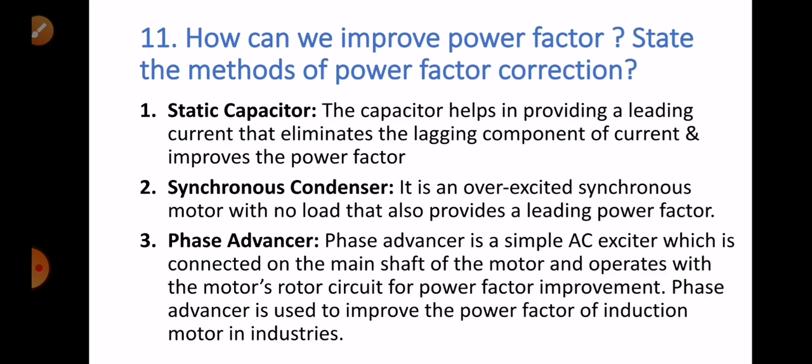Question number eleven: how can we improve power factor? We can improve power factor by three methods. First, static capacitors — the capacitor provides a leading current that eliminates the lagging components and improves the power factor. Second, synchronous condenser — an overexcited synchronous motor with no load that also provides a leading power factor. Third, phase advancer — a simple AC exciter connected on the main shaft of the motor that operates with the motor's rotor circuit for power factor improvement, especially used in induction motors in industries.